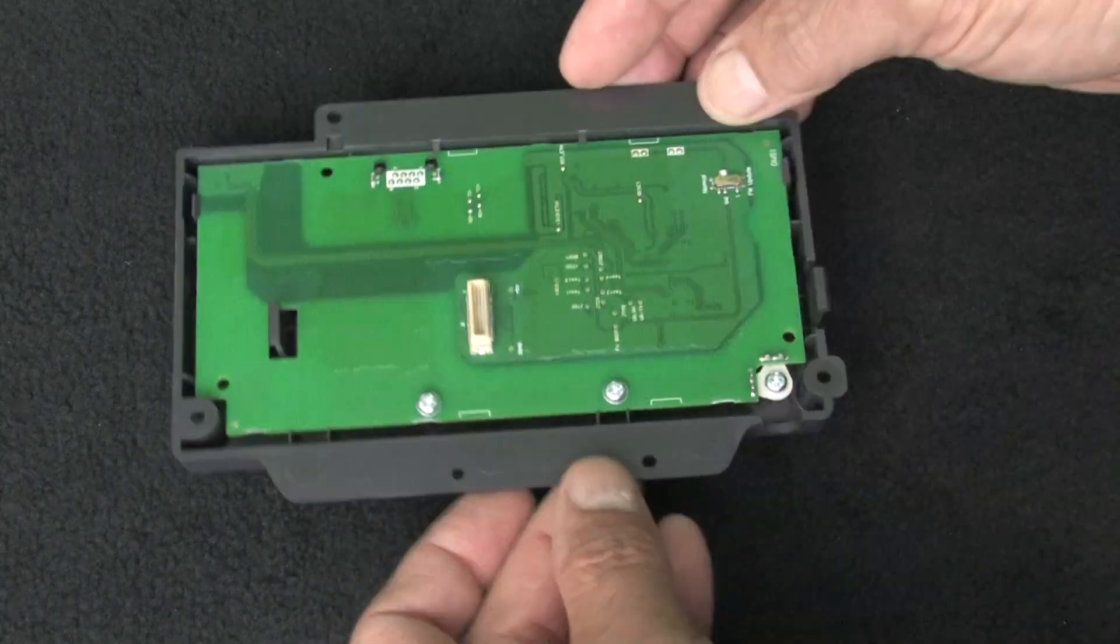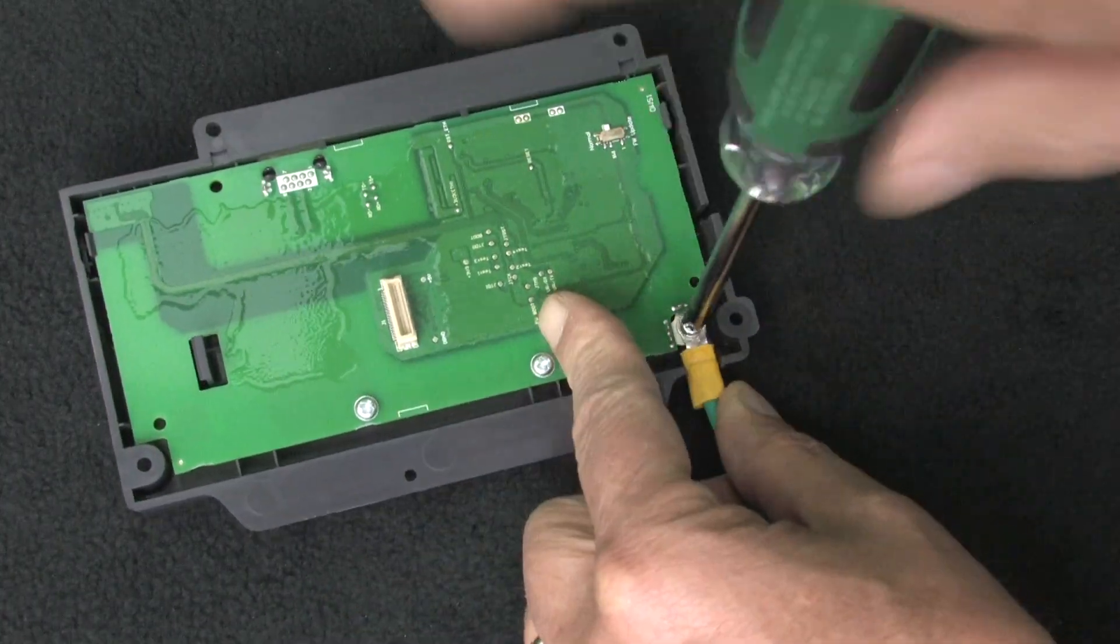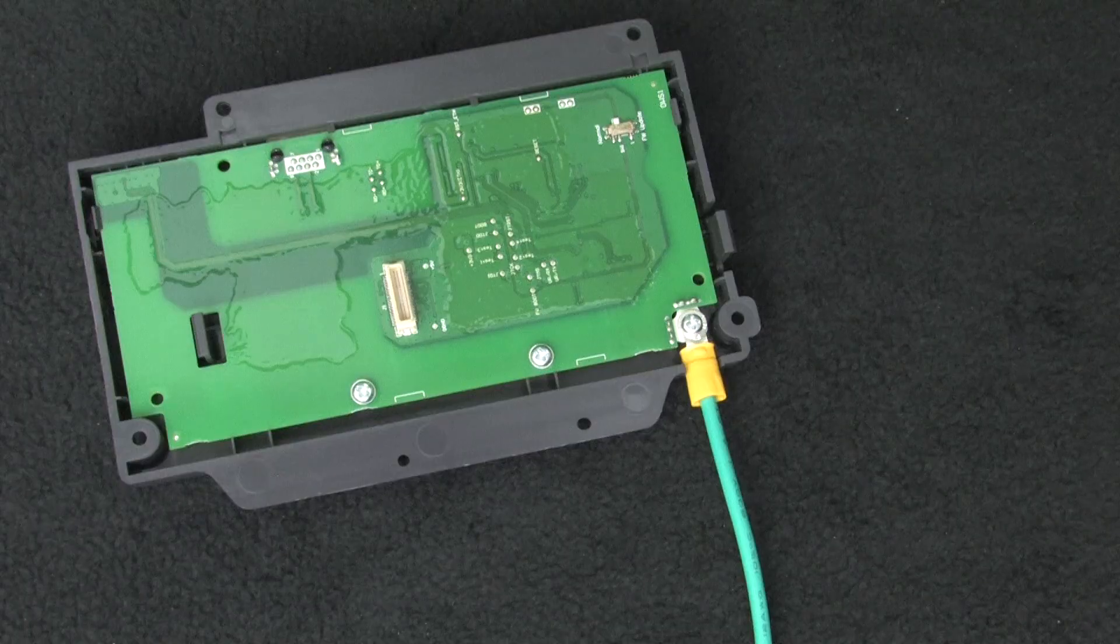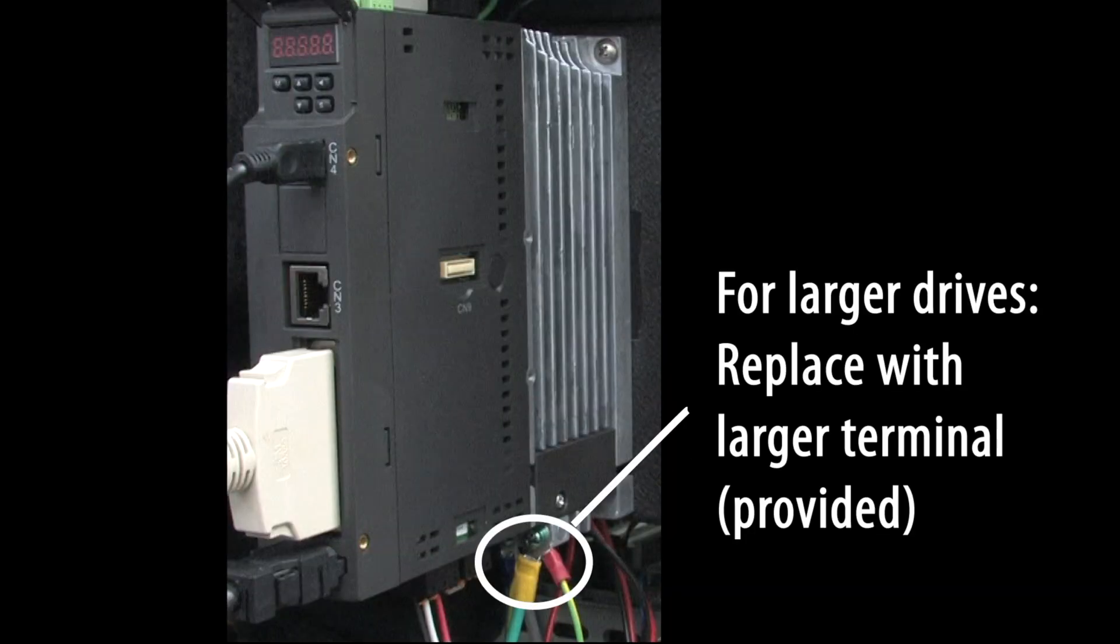On the COM module, connect the provided ground strap. Connect the other end to the drive's ground terminal. If you are using a larger drive, then replace one of the ring terminals with the provided larger ring terminal.